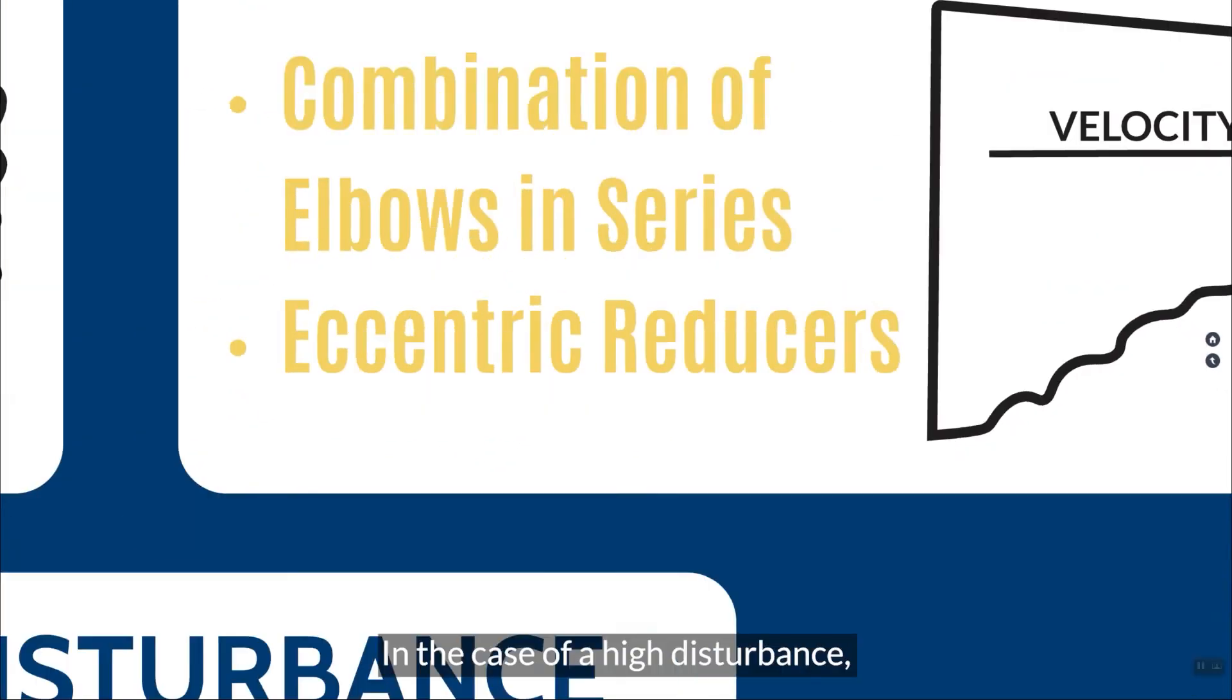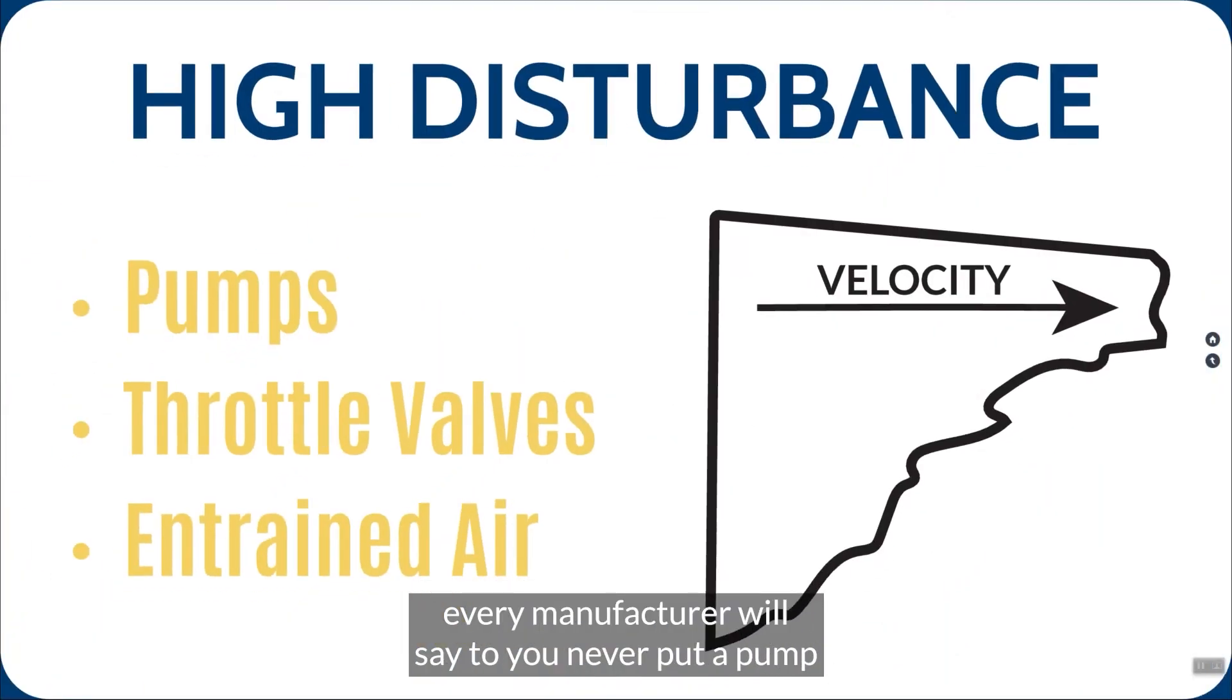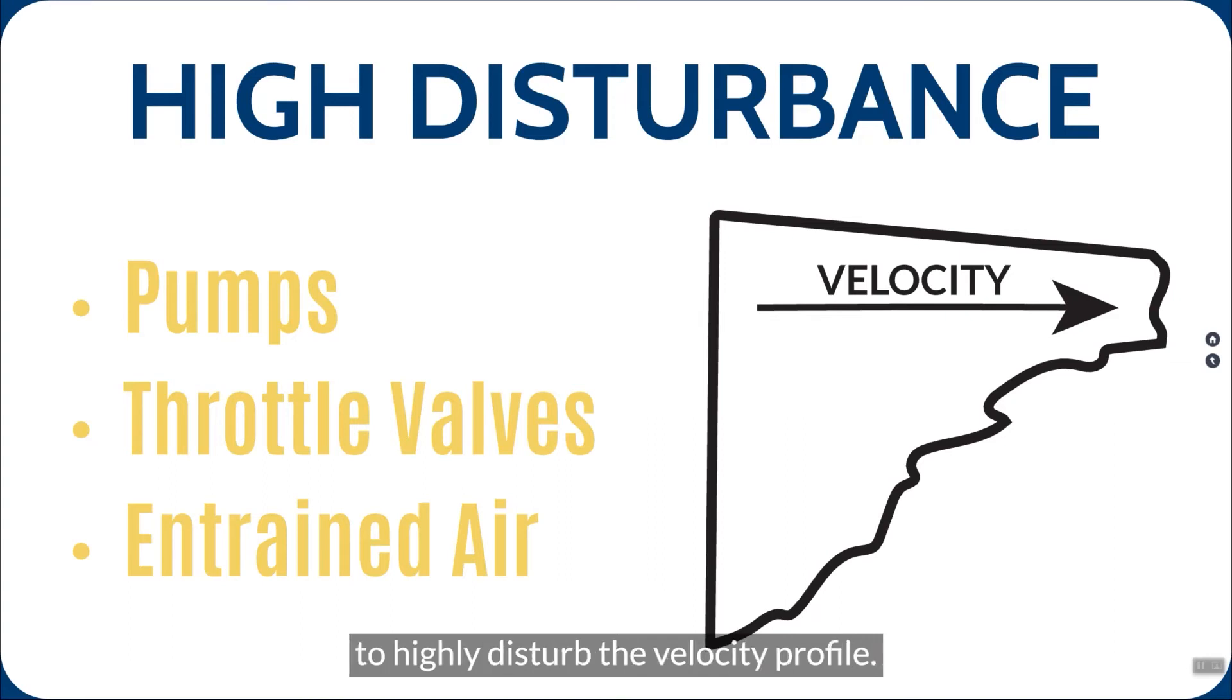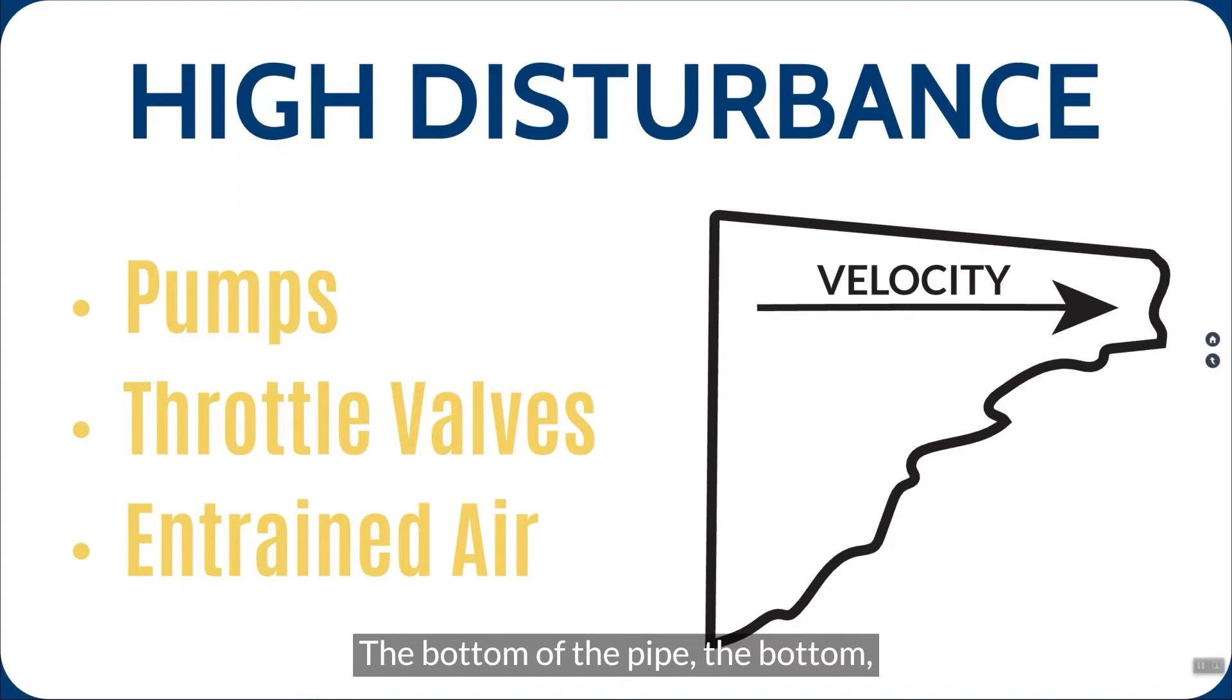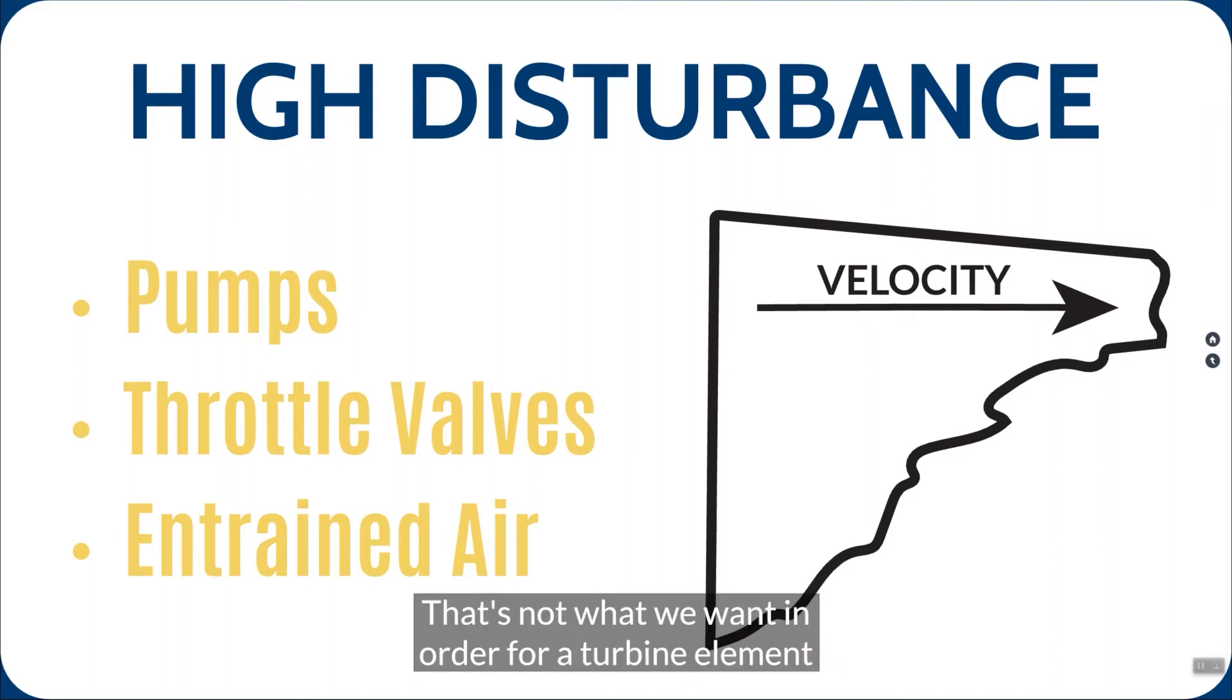In the case of a high disturbance, every manufacturer will say to you, never put a pump or a throttle valve or entrained air before the meter. They're saying that because it's going to highly disturb the velocity profile. I'm going to have something that could look like this. At the top of this pipe, it's moving very fast. The bottom of the pipe, the bottom, probably three quarters of the pipe, moving very slow, very erratic. That's not what we want in order for a turbine element to properly infer the correct volume of water.